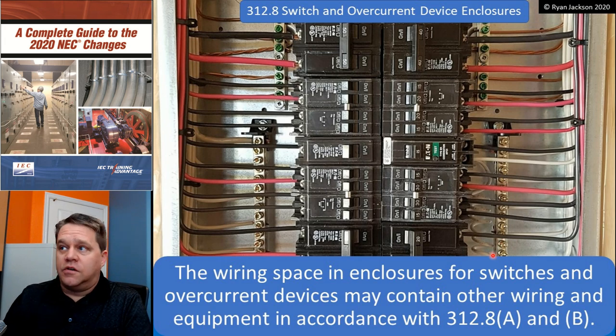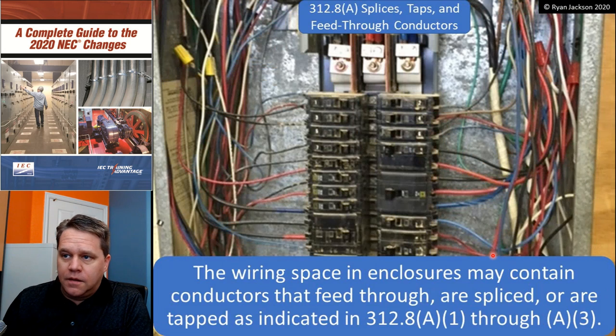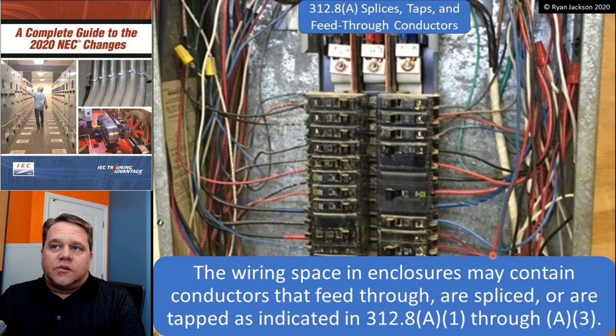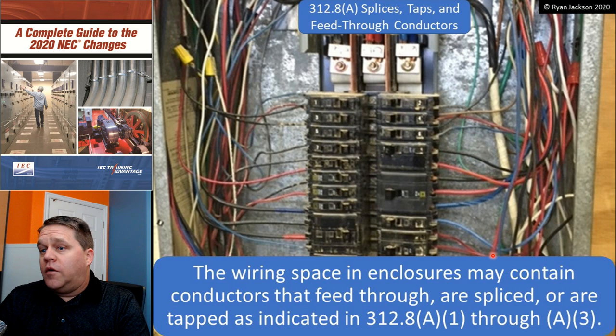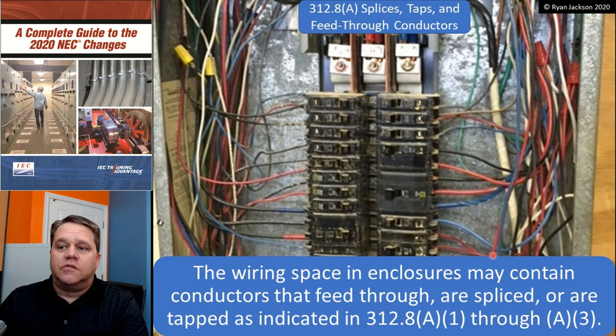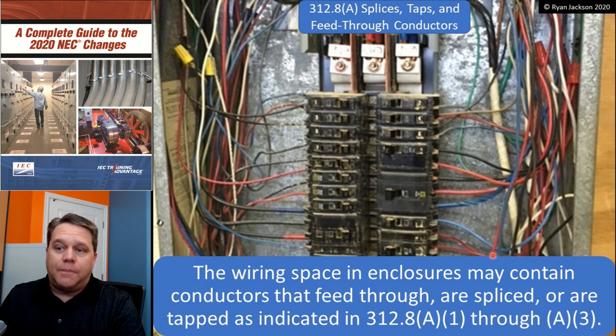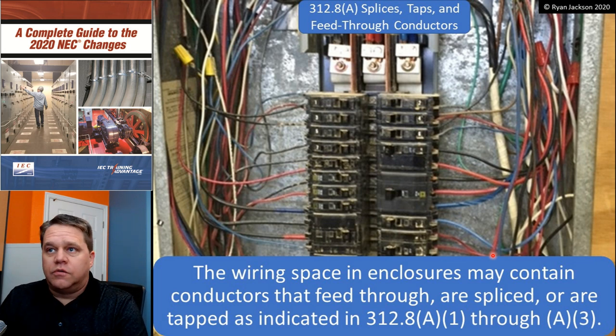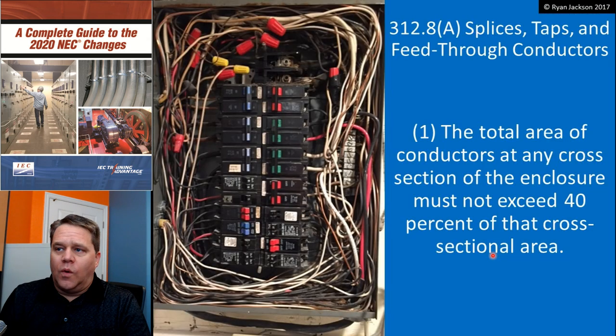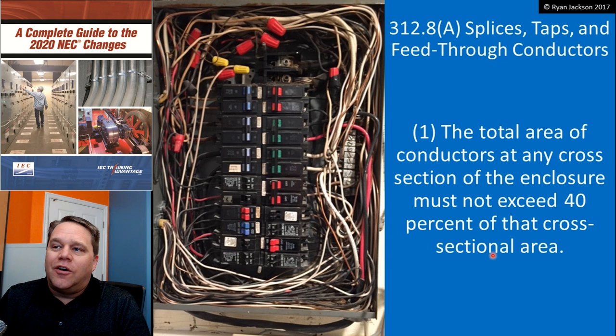The wiring spaces in enclosures for switches and overcurrent devices can contain other stuff in accordance with (A) and (B). Part (A) talks about splices, taps, and feed-through conductors. The wiring space in enclosures can contain conductors that feed through or are spliced or tapped as indicated in items A1, A2, and A3.